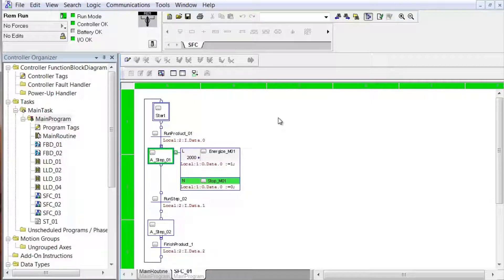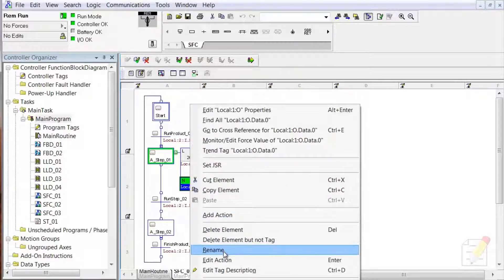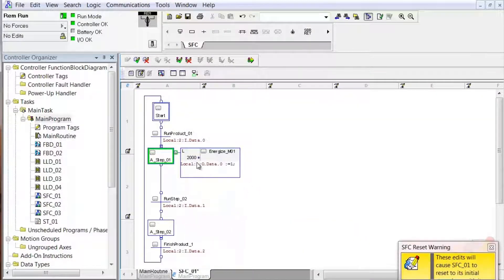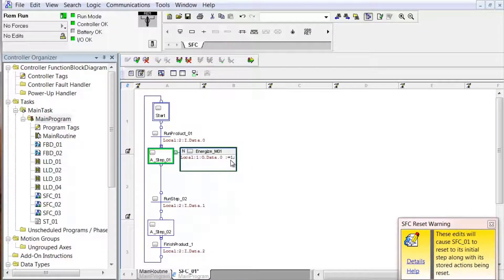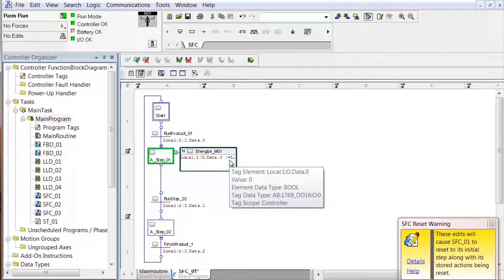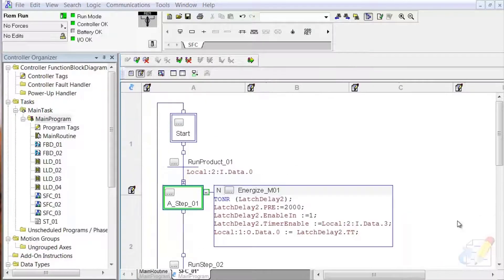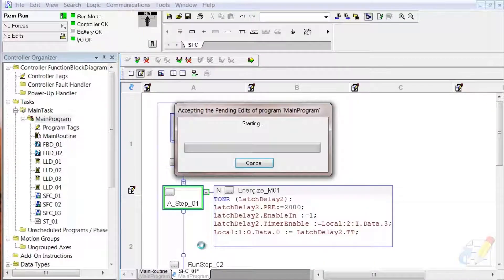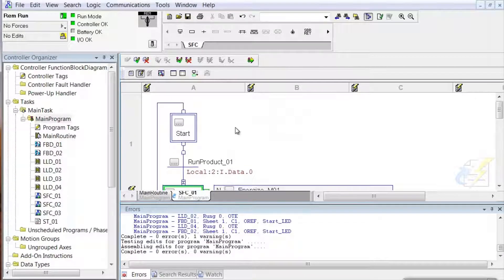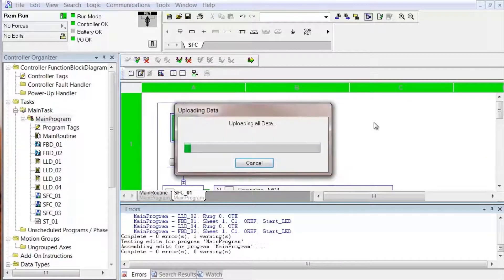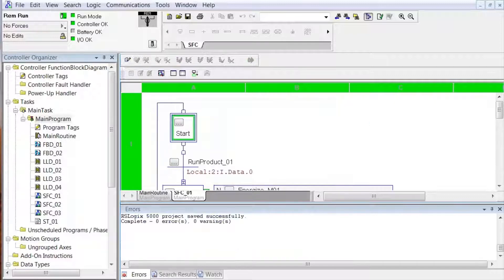In the next step of the lab, open the action, change the qualifier to non-stored, and add structured text as the action. We'll put it in edit mode. I'll delete this one so the name stays — delete element, change this to non-stored, and put structured text in here. I'm going to pause while I add the structured text, because this is not a lecture on structured text. All typed in. Now we're going to finalize all edits. Save — we're actually still in run mode, but I'll save and upload tags. Zero errors, zero warnings.